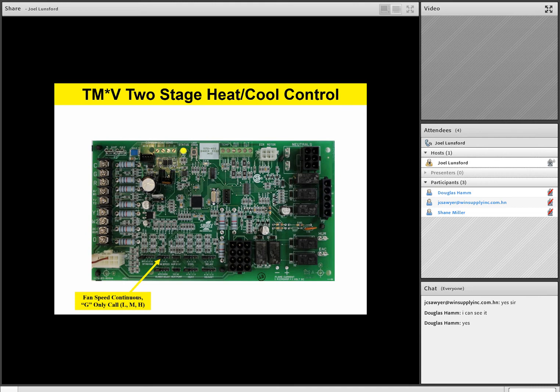So this fan speed is for continuous fan operation. In other words, you just have a G only call from the thermostat on the board for continuous fan operation: high, medium, low. Low is going to be about 35% airflow, medium is going to be about 50% airflow, and high is going to be 100% cooling airflow. Any questions on that?